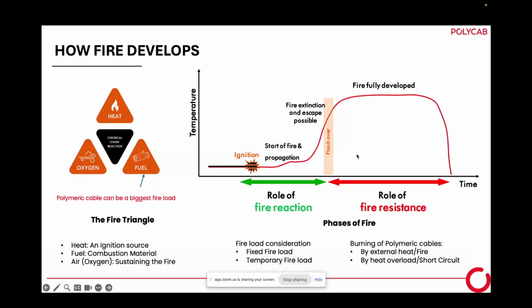This is where fire survival cable comes into the picture. If we have a fire survival cable, it can operate up to 950-degree temperature, and important devices like lift, fire alarm system, water sprinkler, and pump will all continue to operate. We give a guarantee of 3 hours of operation.